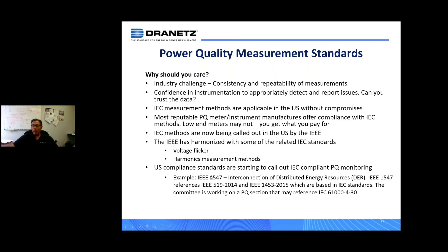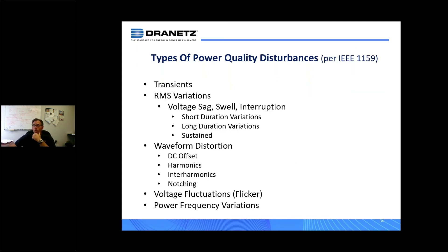In other areas such as voltage flicker and harmonic methods, the IEEE is harmonizing with IEC requirements. IEEE 1547, for distributed energy resources — solar, wind, and other alternative energy interconnecting to the grid — references some of these measurement techniques and addresses not only safety but also power quality issues at the point where power is pushed back onto the grid. Going through the power quality disturbance types quickly: a transient is a short-term change — the microseconds and milliseconds kind — basically a spike that can blow something up or lock a device up.